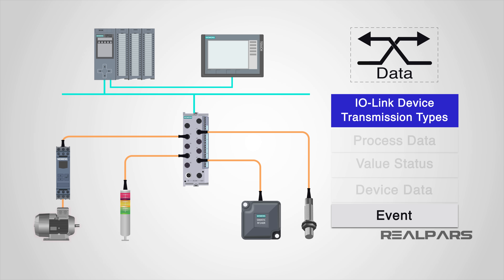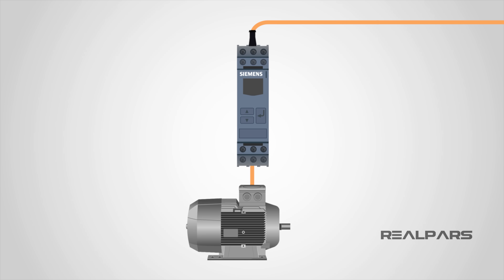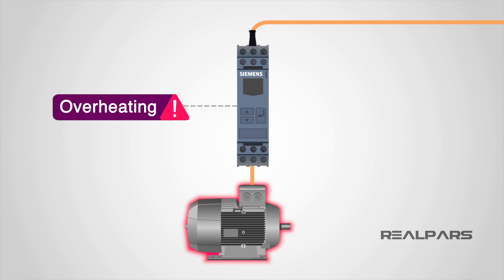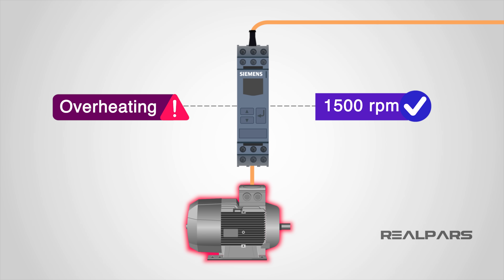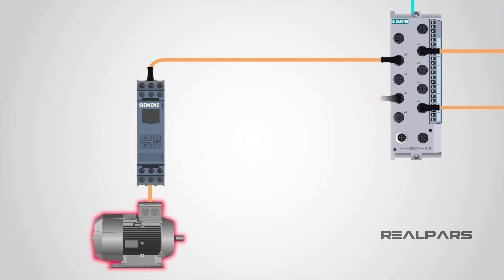A device is able to trigger an event, which in turn signals the presence of an event to the IO-Link master. An example of an event is an error or warning message, such as a short circuit or a device that is overheating. This information can be used to display indicators or messages on HMI devices, such as error messages signaling a wire break or a communication failure, once the IO-Link master has processed the message to the high-level controller. The transmission of device parameters and events occurs independently from the cyclic transmission of process data, so critical messages do not have to queue until already buffered messages are sent.